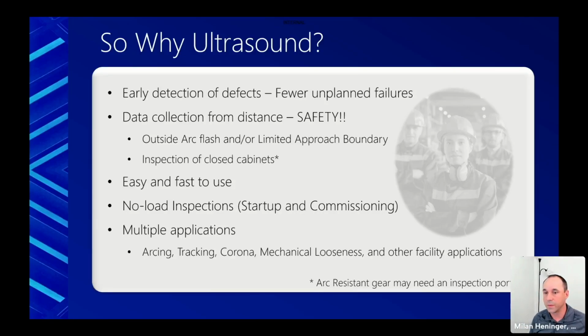And finally, we do have multiple applications. As we saw from the poll, there's all of these facility applications of compressed air leaks and bearings and lubrication routes, things of that nature. But on the electrical side, which I'm focusing on today, we have arcing, tracking, corona, and mechanical looseness that are all things that we can easily detect with ultrasound via the partial discharge that they typically create, or in the case of mechanical looseness, some of the rattling and the friction that that's causing.